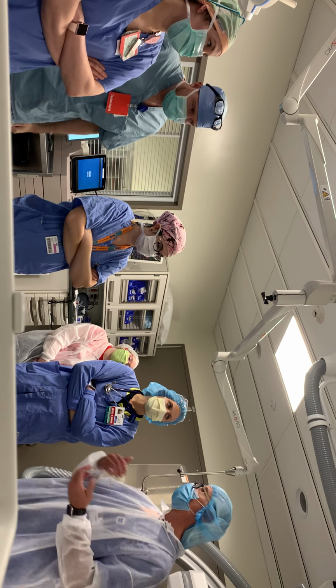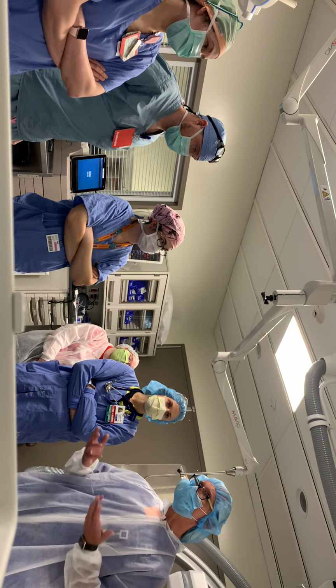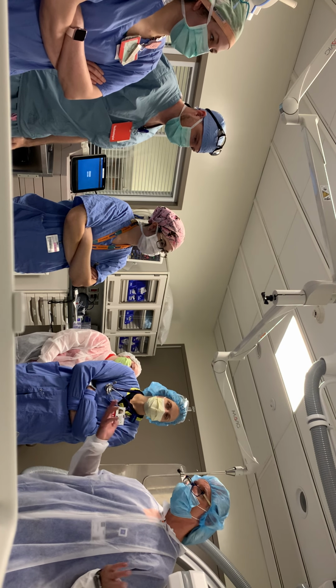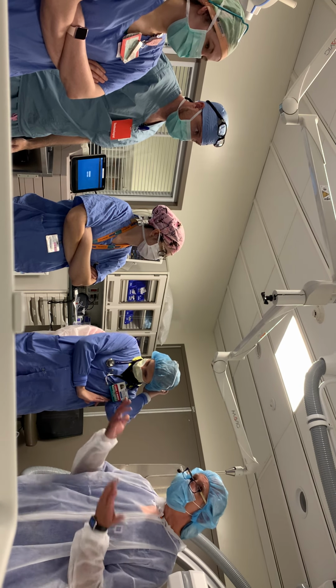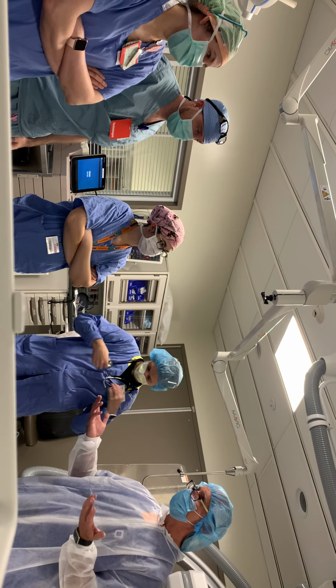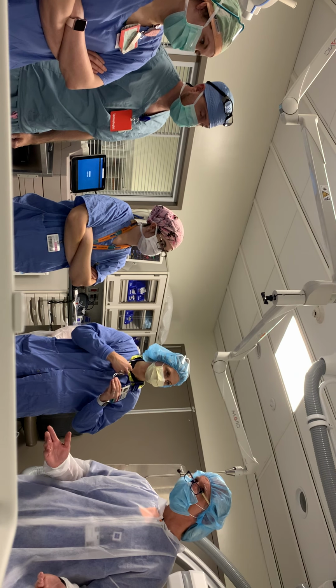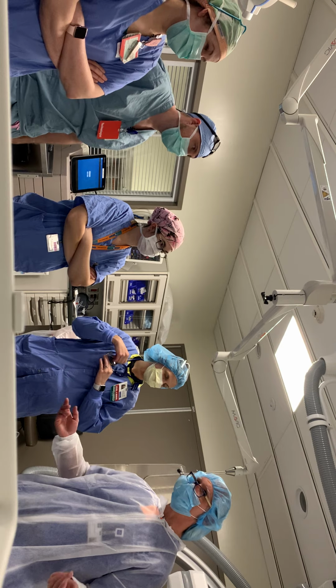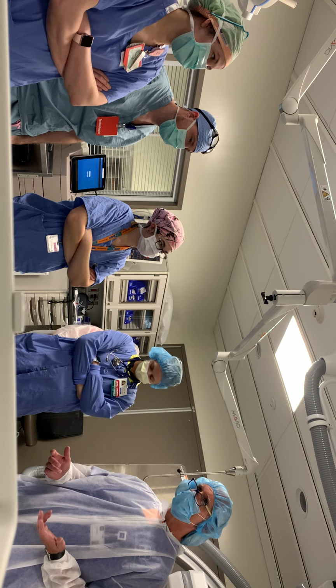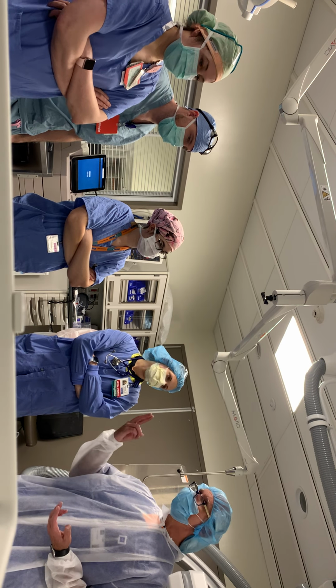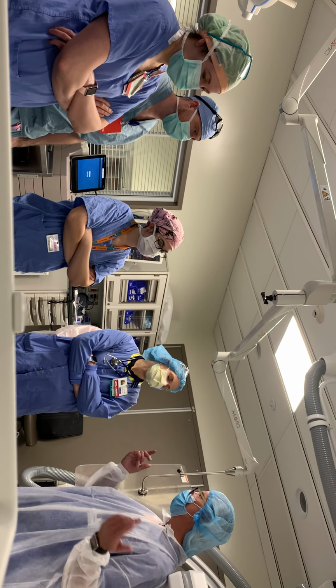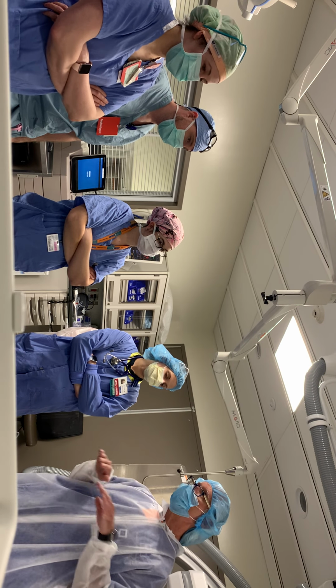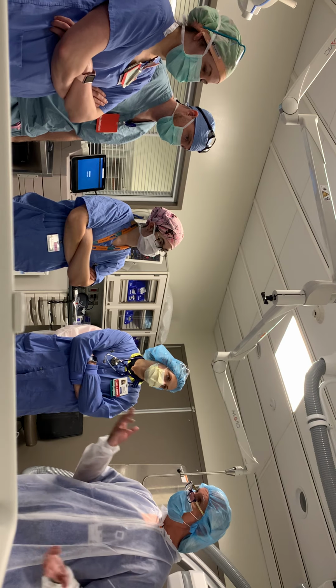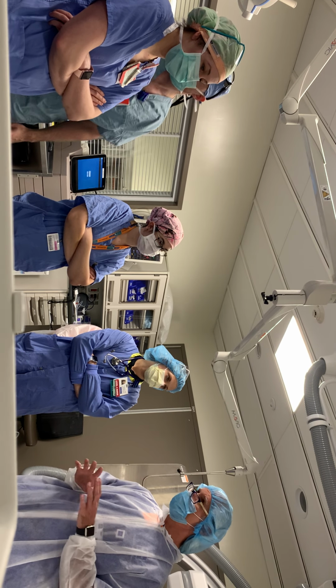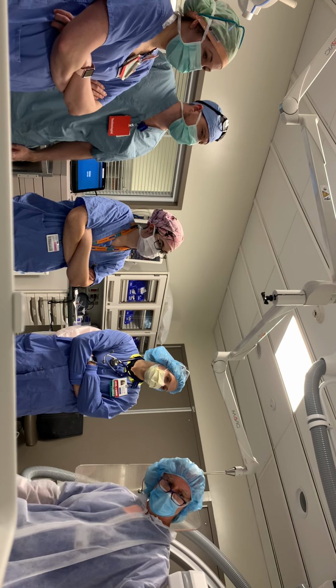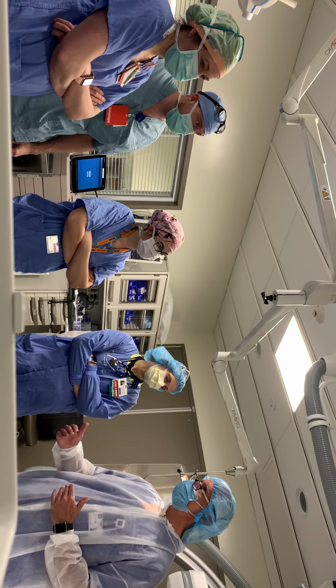Understand, when you are zeroing the system, you're zeroing it, first and foremost, to atmospheric pressure. So in reality, just to make things a little bit more complex, you don't have to have any fluid in there to zero. You can zero it completely dry and then put the fluid in later. When you're zeroing, you're zeroing two things: atmospheric pressure, which is what you do on the system, and hydrostatic pressure, which is the weight of the fluid in the lines. You do that zero by physically ensuring that it is at heart level.